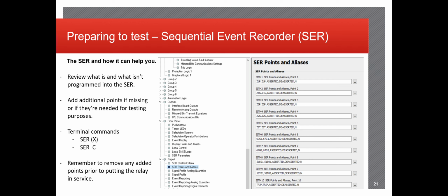Remember to remove any added points prior to putting the relay in service. Again, this is especially important for setting up that spare output contact. If you set that up and you run your last test and you just unplugged everything and walked away, that output still has whatever relay element you put into it. Meaning if someone were to go back and run a different test or whatnot and see that that element's picked up for some reason, they're going to be questioning it. As well as if they don't do their due diligence later down the line and they end up utilizing that output, that could lead to a misoperation without even starting the relay testing, which would be really bad.